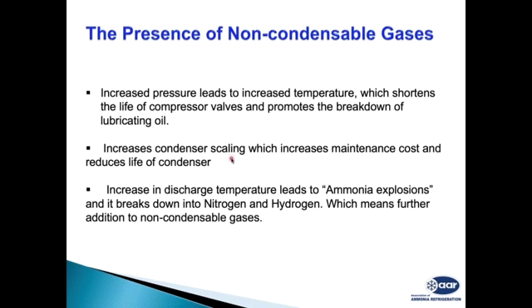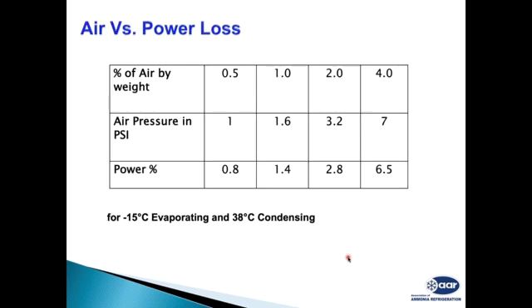Increase in temperature results in increased scaling on the condensers, where we now need frequent cleaning, which increases the maintenance cost of the condenser. Increase in discharge temperature, as I explained earlier, leads to ammonia explosion, and ammonia may break into nitrogen and hydrogen, which are again non-condensable gases.